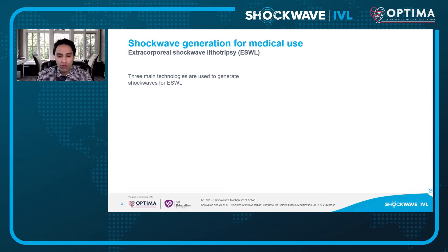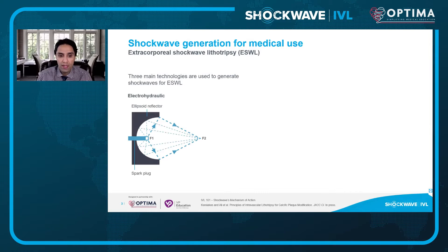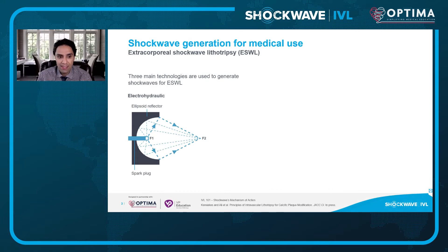Shockwave is generated for medical use traditionally based on extracorporeal shockwave lithotripsy, which is used for renal calculi. There are three main technologies used to generate shockwaves for external shockwave lithotripsy. The first is basically a spark plug with two electrodes in which an electrical arc is created between the two in a fluid-filled cavity, creating unfocused energy that becomes focused based on a reflection from the ellipsoidal reflector — kind of like a flashlight focuses light to go forward instead of spreading everywhere.